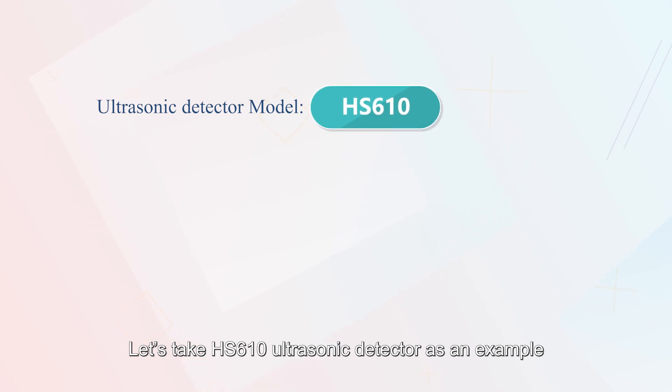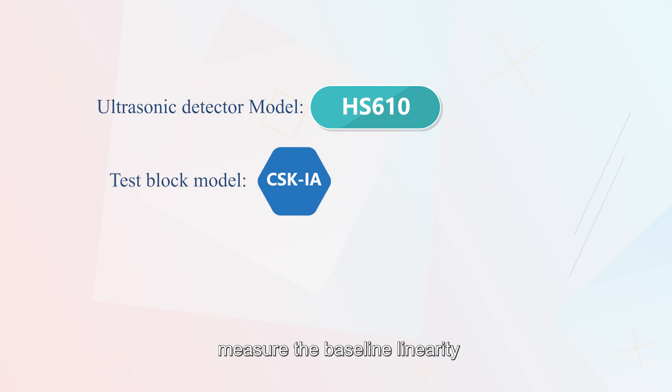Let's take HS610 ultrasonic detector as an example to explain how to draw DAC curve. First, measure the baseline, linearity, and angle probe k-value on the CSK-IA test block.